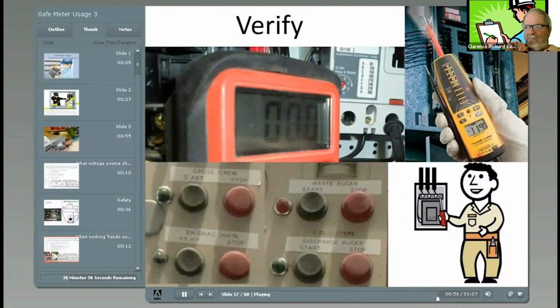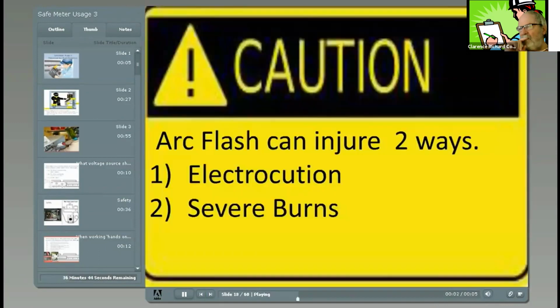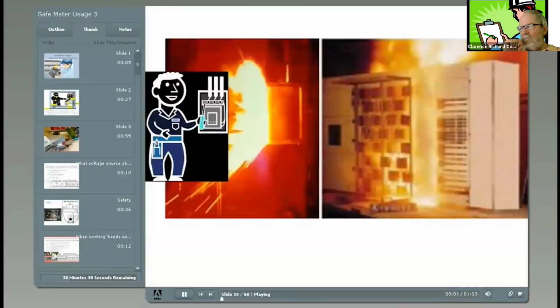OSHA requires arc flash personal protective equipment, or PPE, to be worn in cases where personnel are exposed to high energy short circuits and electrocution. Therefore, minimizing exposure to the inside of high voltage cabinets is prudent. Injured two ways: electrocution and severe burns. High voltage short circuit happens. Explosions like this can happen. Being in the vicinity without the PPE can cause serious injury.